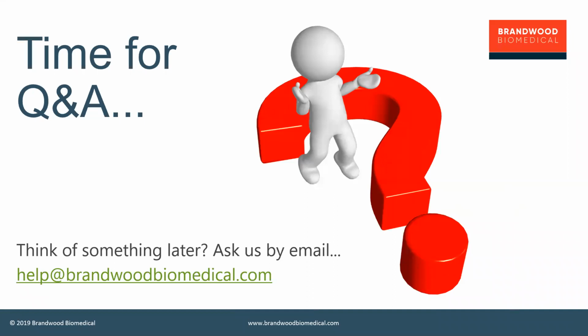And particular attention has to be paid to, Part H, the confirmation that the device meets any defined chemical or physical specifications. So this is actually about verification. If your specification defines a chemical or a physical characteristic, then you have to validate for it. That's really what this says.